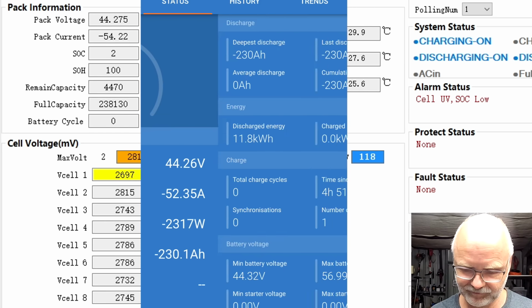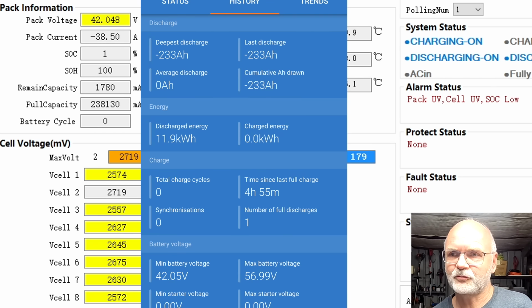And we have discharged 11.9 kilowatt hours. So more than the battery is rated for. All batteries in yellow except cell number 2, which is our highest. 42 volts. I'm not sure when the inverter shuts down, but this is incredible. 233 ampere hours discharged. 11.9. Do we see 12? No, we don't. The inverter is really low.